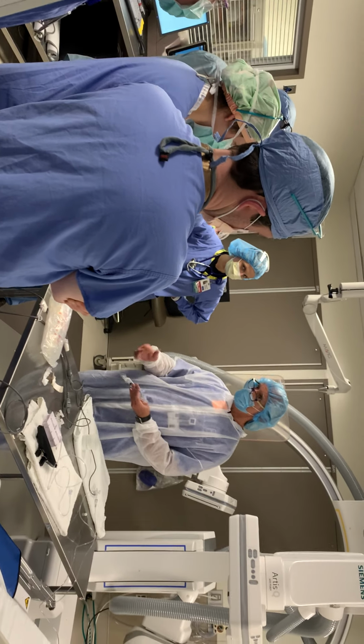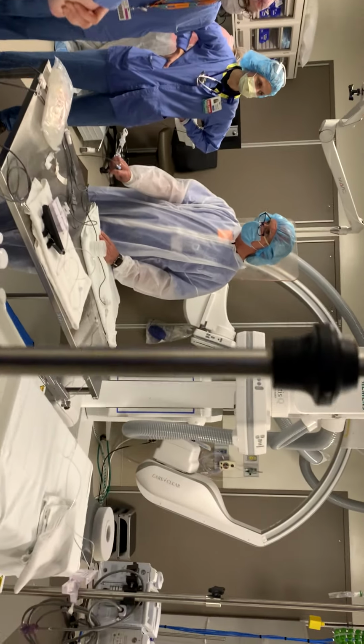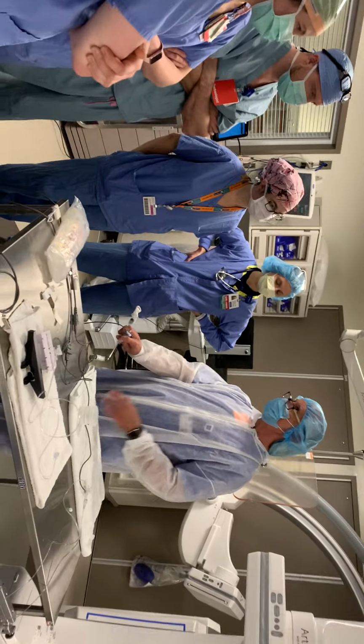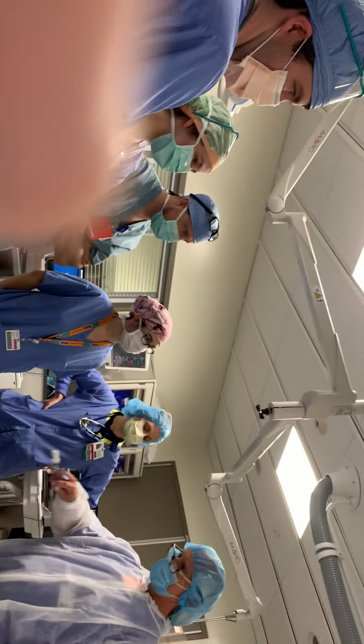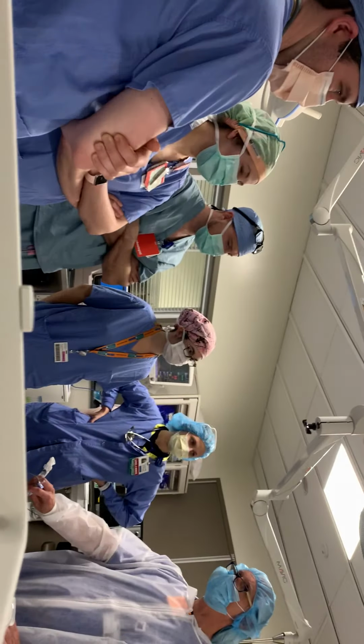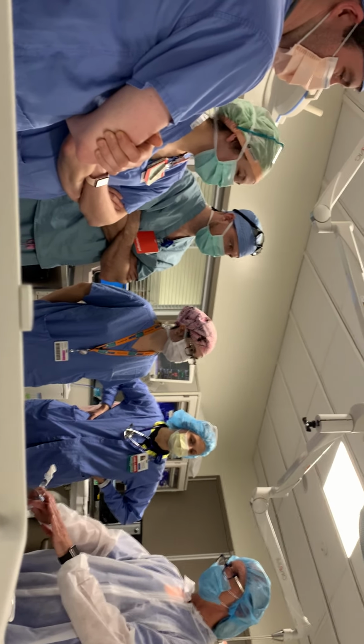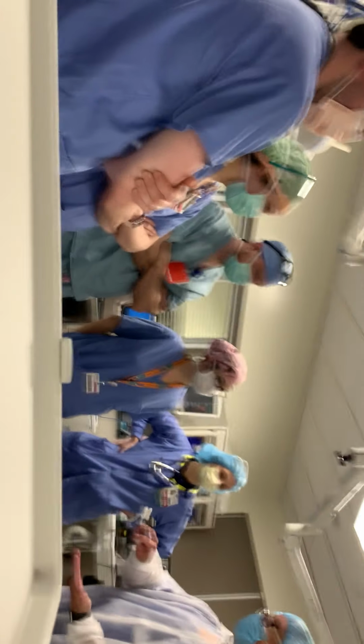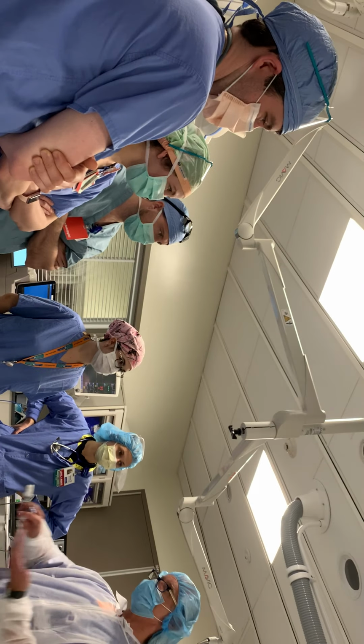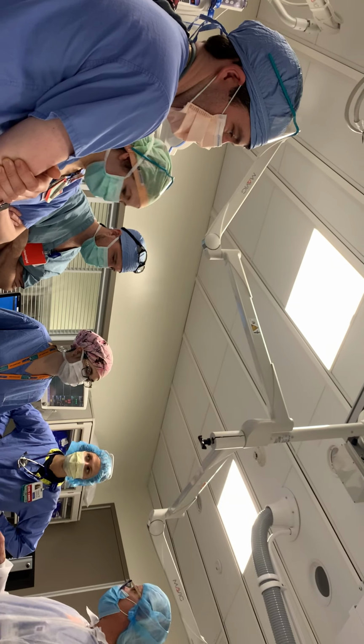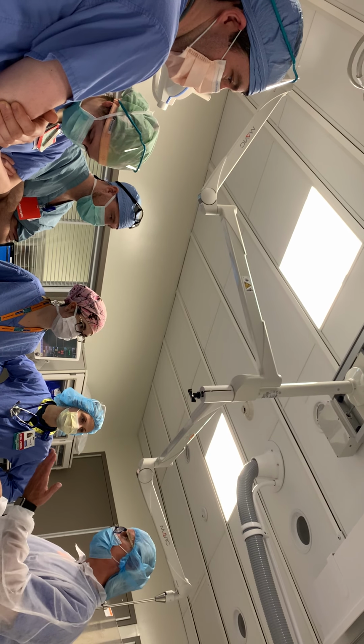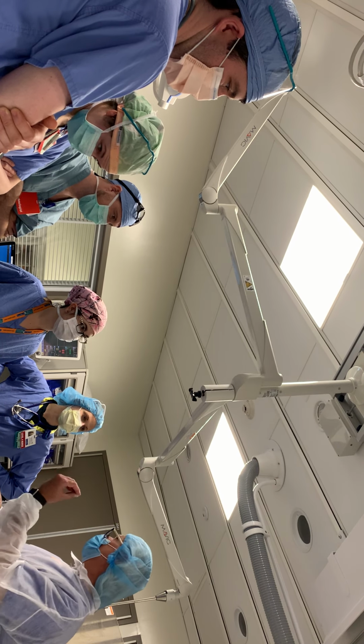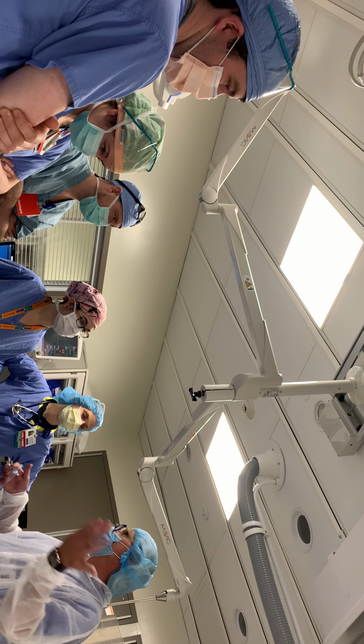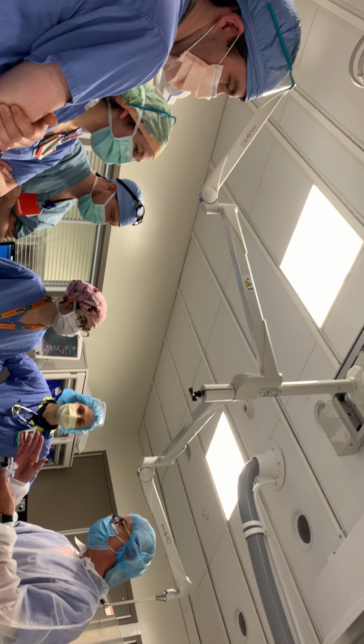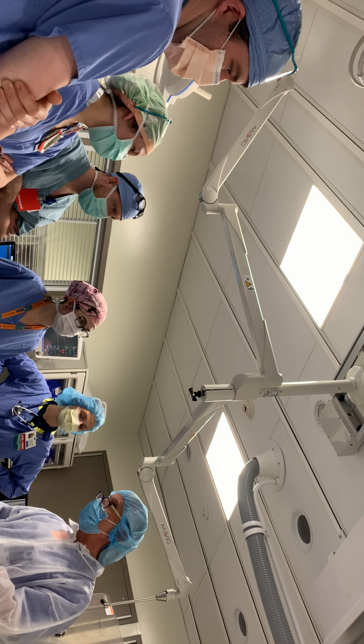But it has to physically be at heart level when you're taking your pressure measurement. And if you're taking multiple pressure measurements that you will then want to compare to each other, you have to make sure that you put it back to the same level every time you take a pressure measurement. Because if you're this far off of where you were before, your pressures are going to be off. Now, if there are arterial pressures, it's not nearly as bad. We're talking about venous pressures, little differences make a big difference. So I think that might be what's led you to go to option B.